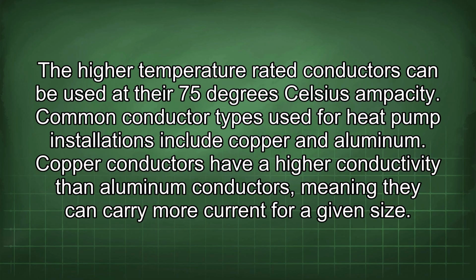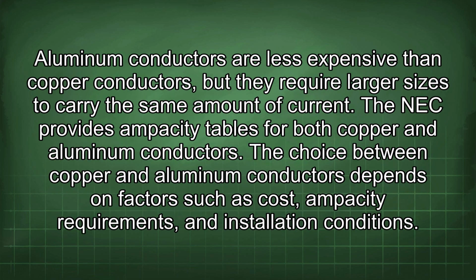Common conductor types used for heat pump installations include copper and aluminum. Copper conductors have a higher conductivity than aluminum conductors, meaning they can carry more current for a given size. Aluminum conductors are less expensive than copper conductors, but they require larger sizes to carry the same amount of current. The NEC provides ampacity tables for both copper and aluminum conductors. The choice between copper and aluminum conductors depends on factors such as cost, ampacity requirements, and installation conditions.